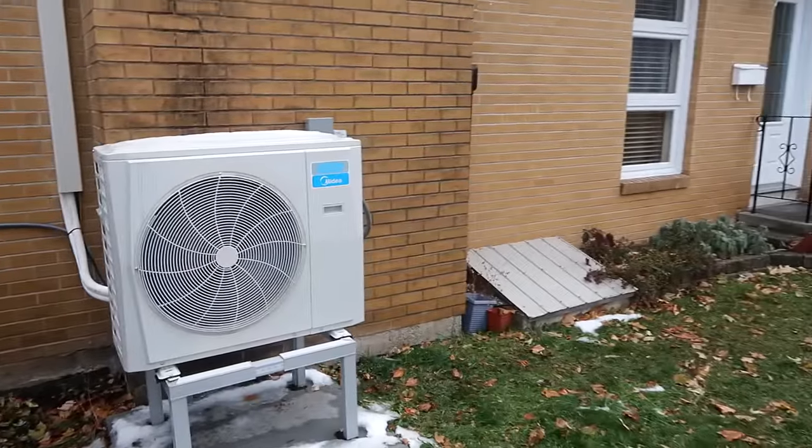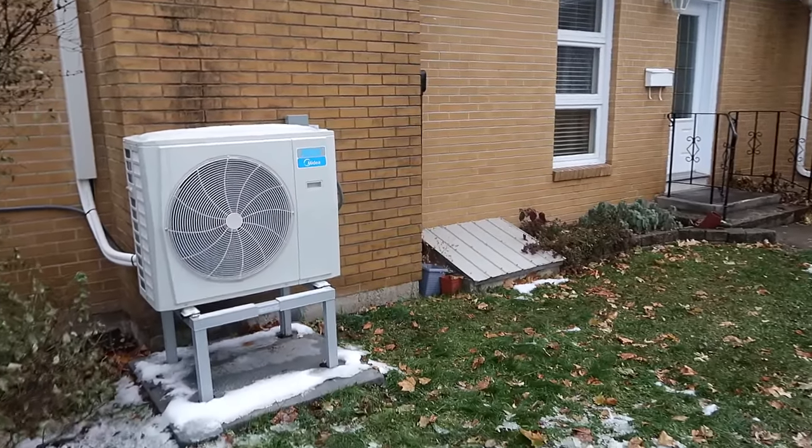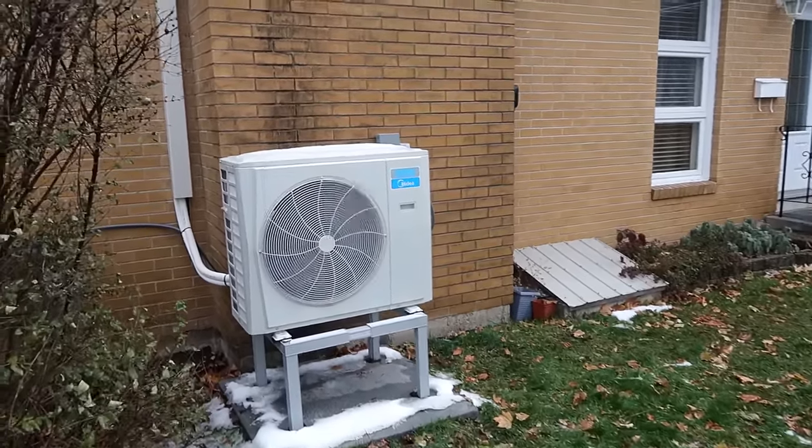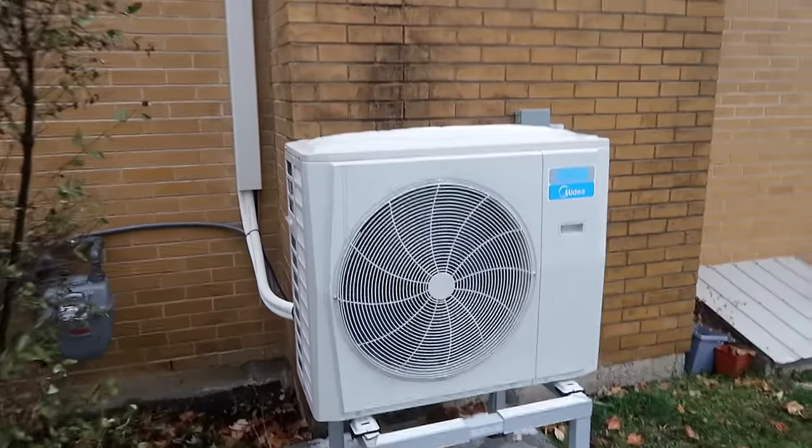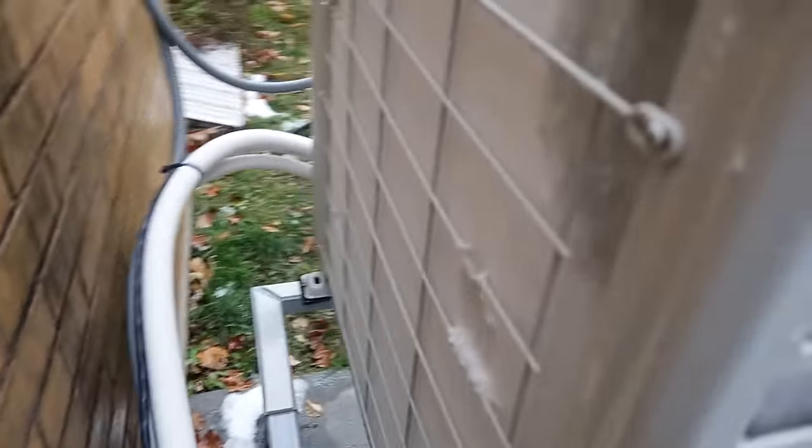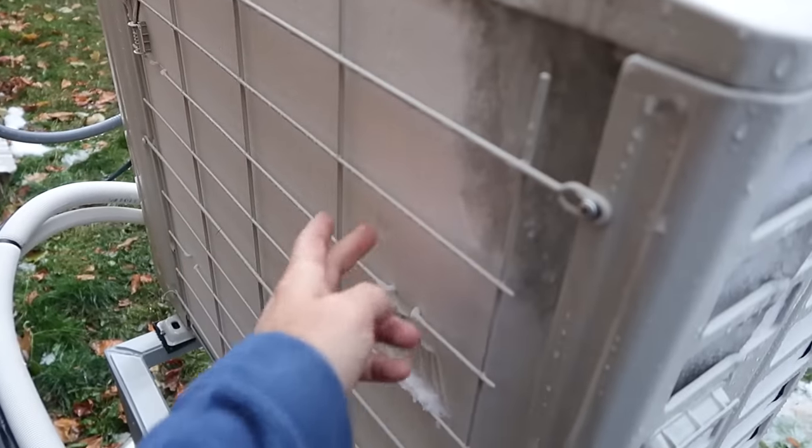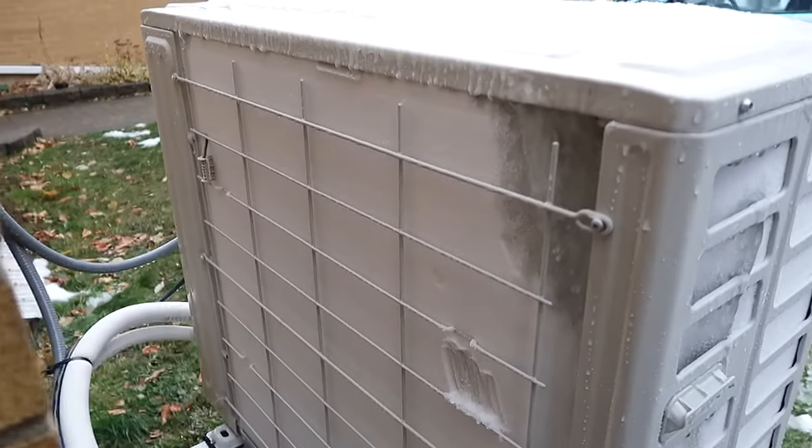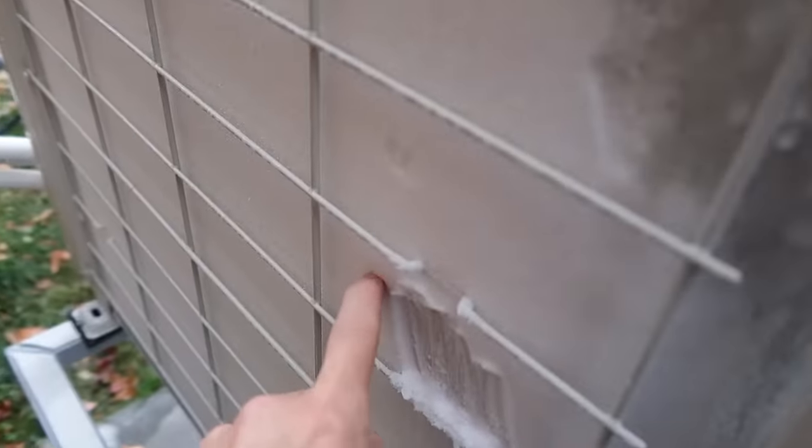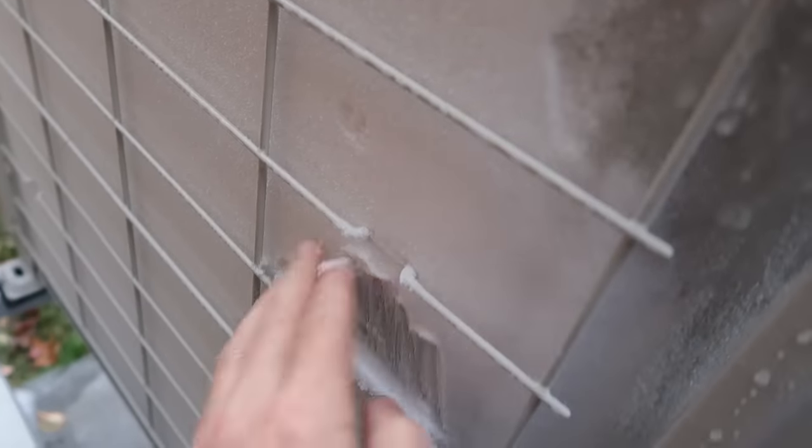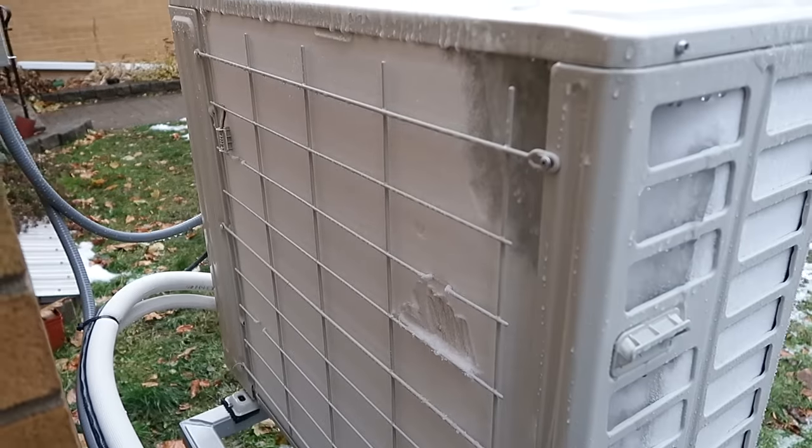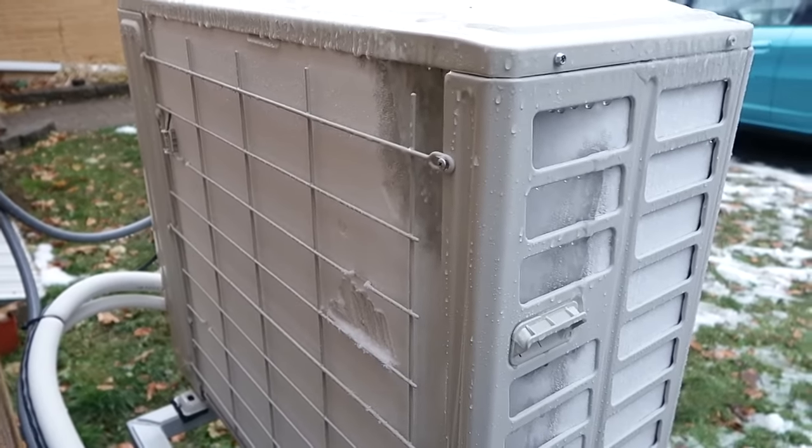Now the mini splits were working really well all through the fall, but then when things got around freezing, this happened. The temperature is well above zero right now, three degrees Celsius, but this thing is all iced up and it wouldn't be iced up if there's air flowing through here, this part wouldn't get cold enough to actually freeze on there, but because there's no air going through because it's completely iced up, it basically gets cold because it's not getting any air through it.